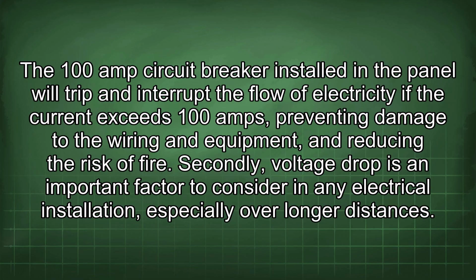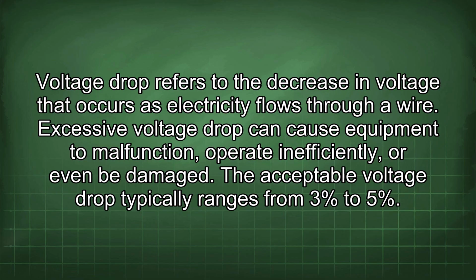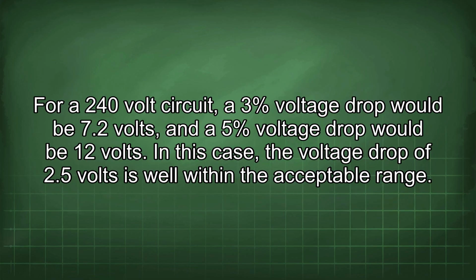Secondly, voltage drop is an important factor to consider in any electrical installation, especially over longer distances. Voltage drop refers to the decrease in voltage that occurs as electricity flows through a wire. Excessive voltage drop can cause equipment to malfunction, operate inefficiently, or even be damaged. The acceptable voltage drop typically ranges from 3% to 5%. For a 240-volt circuit, a 3% voltage drop would be 7.2 volts, and a 5% voltage drop would be 12 volts. In this case, the voltage drop of 2.5 volts is well within the acceptable range.